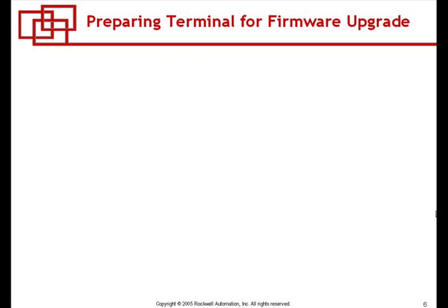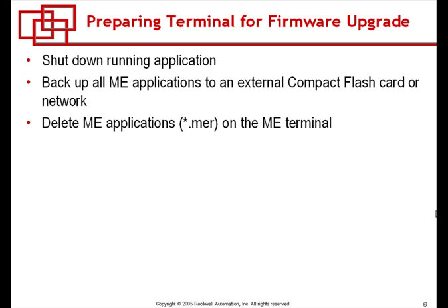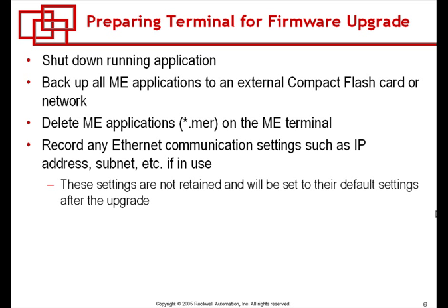In preparing the terminal for firmware upgrade, shut down any running application. Back up all ME applications to an external compact flash card or network. Delete all ME applications or MER files on the ME terminal. Record any Ethernet communications such as IP address, subnet, etc.